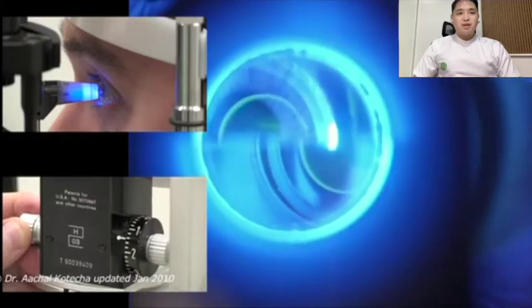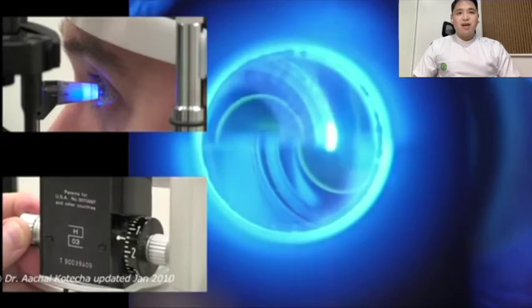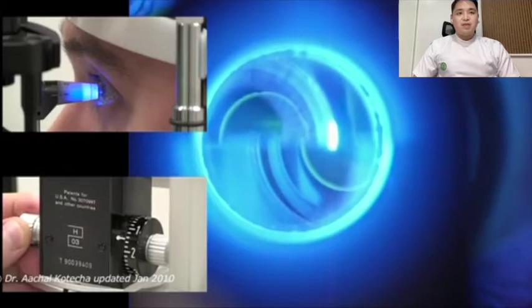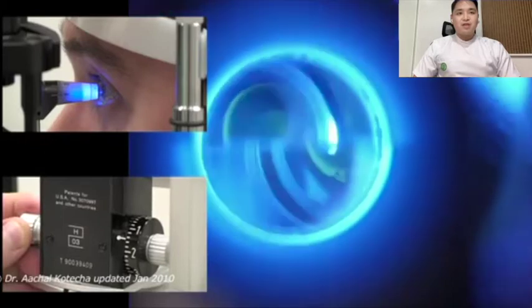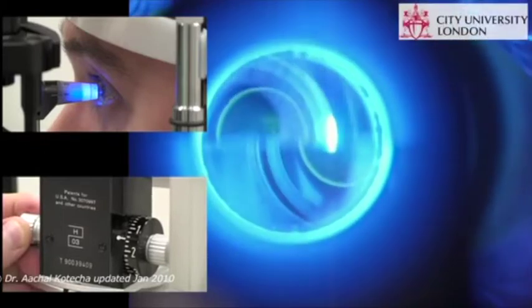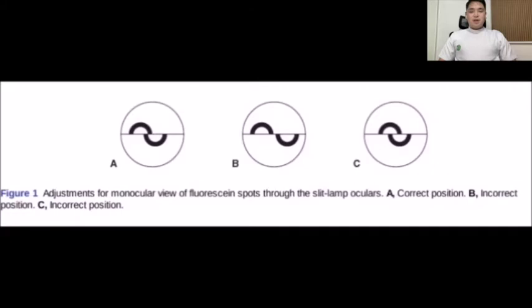The semicircles can be viewed monocularly through only one of the slit lamp's oculars. In most slit lamps, the semicircles are viewed through the left ocular. If the semicircles are separated, as in figure 1b, the pressure reading will be too low. If the semicircles overlap, as in figure 1c, the pressure reading will be too high.